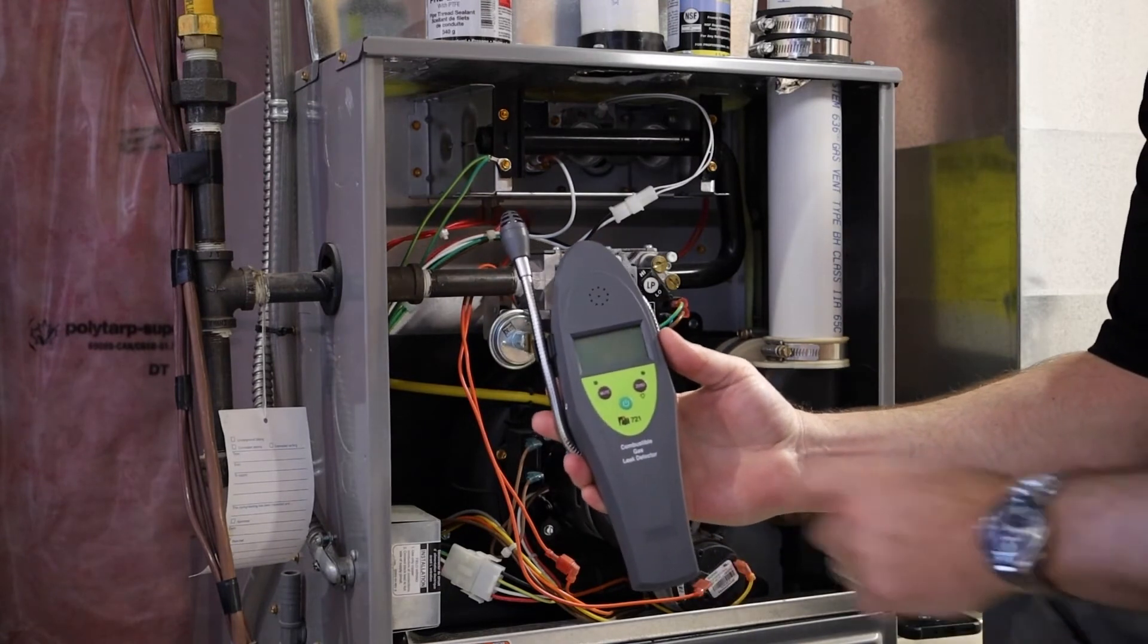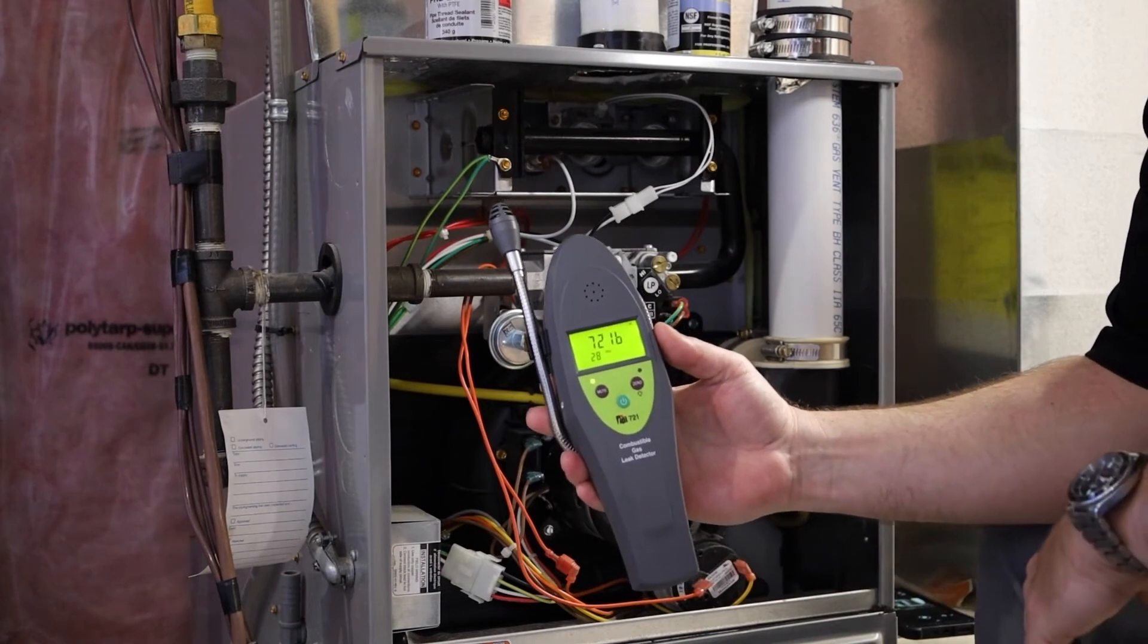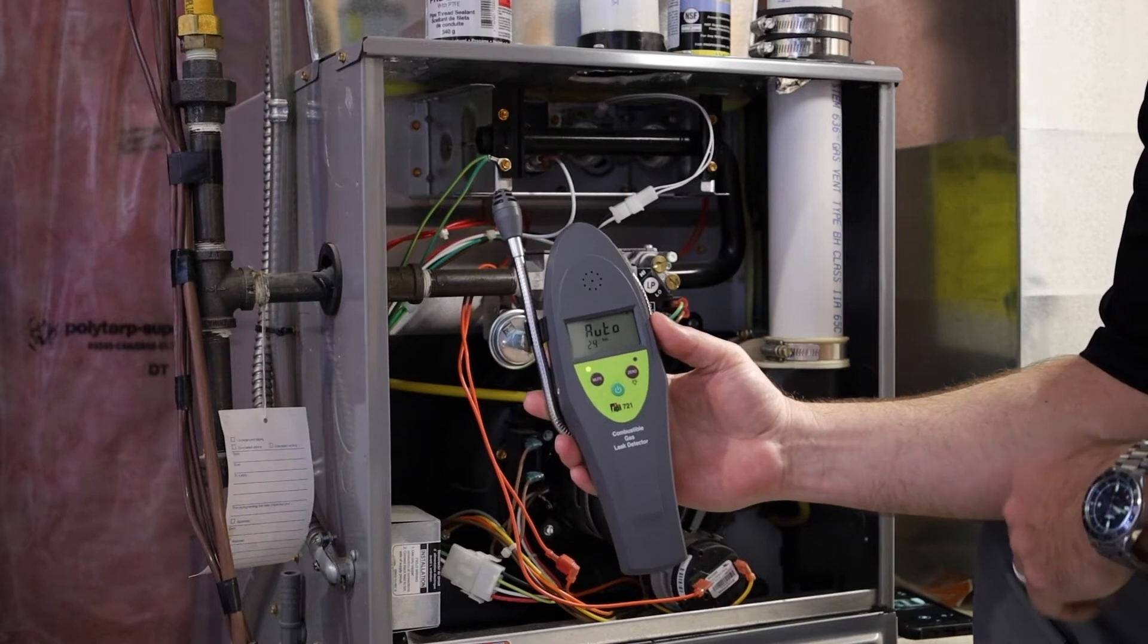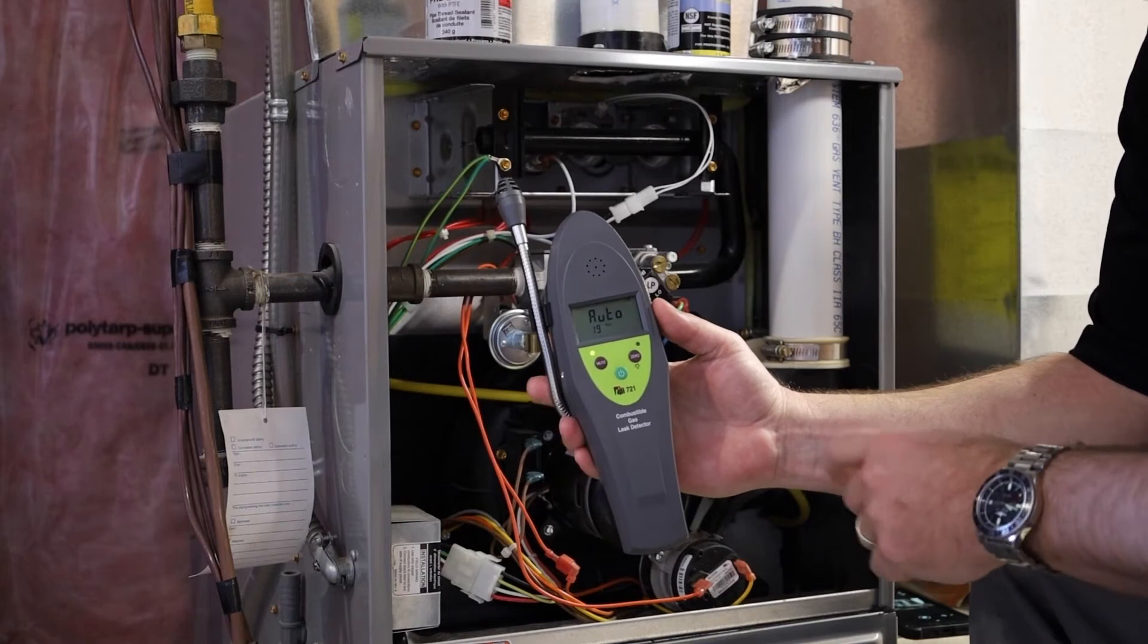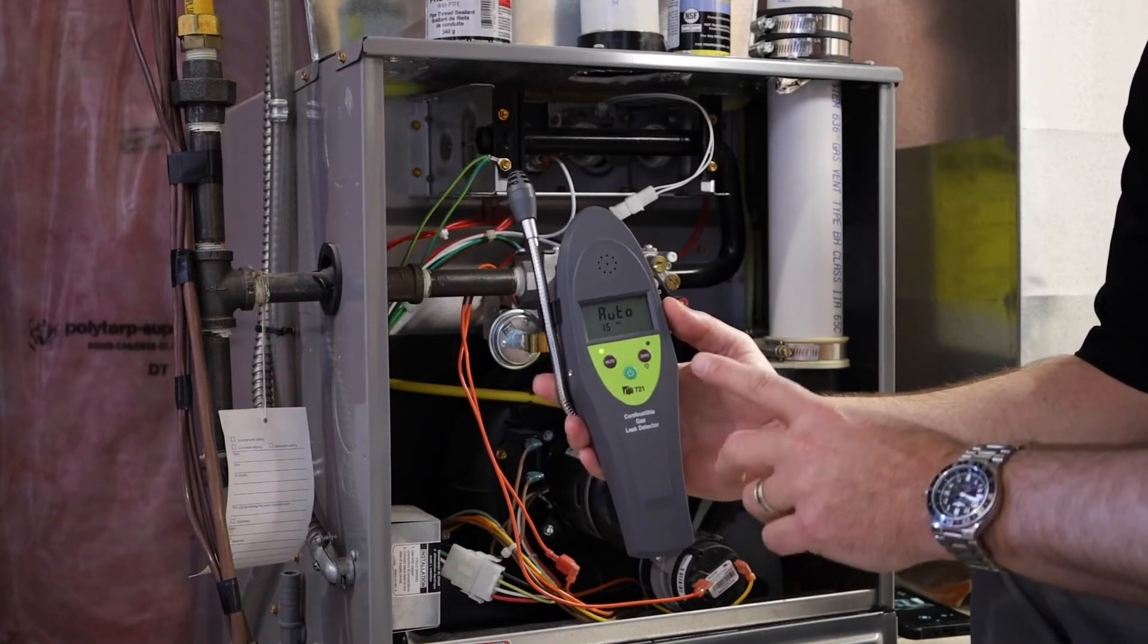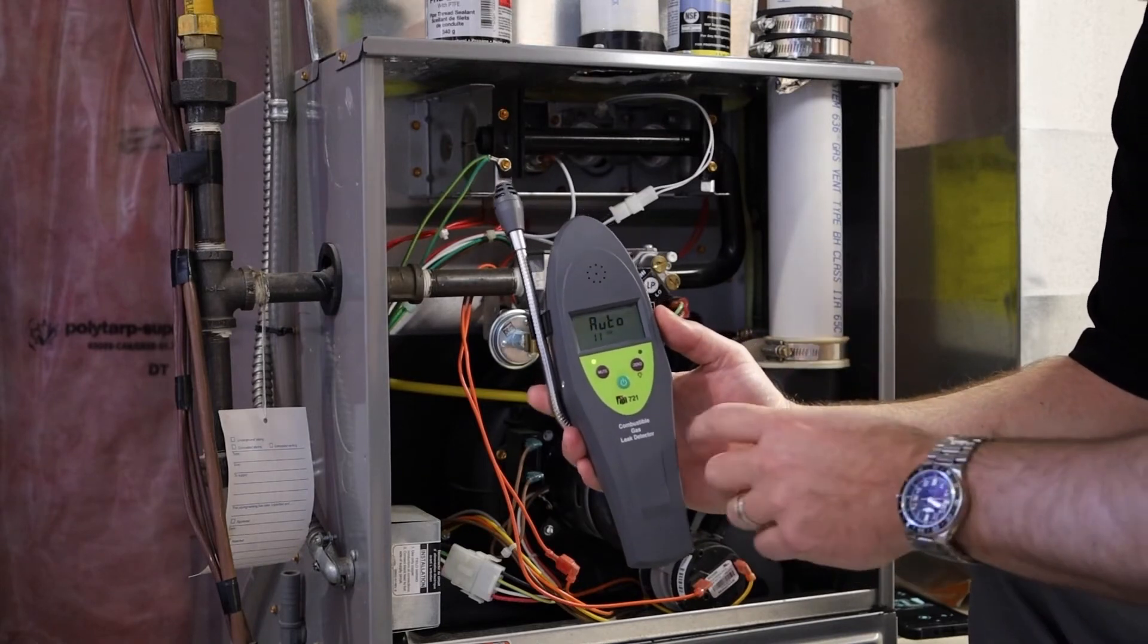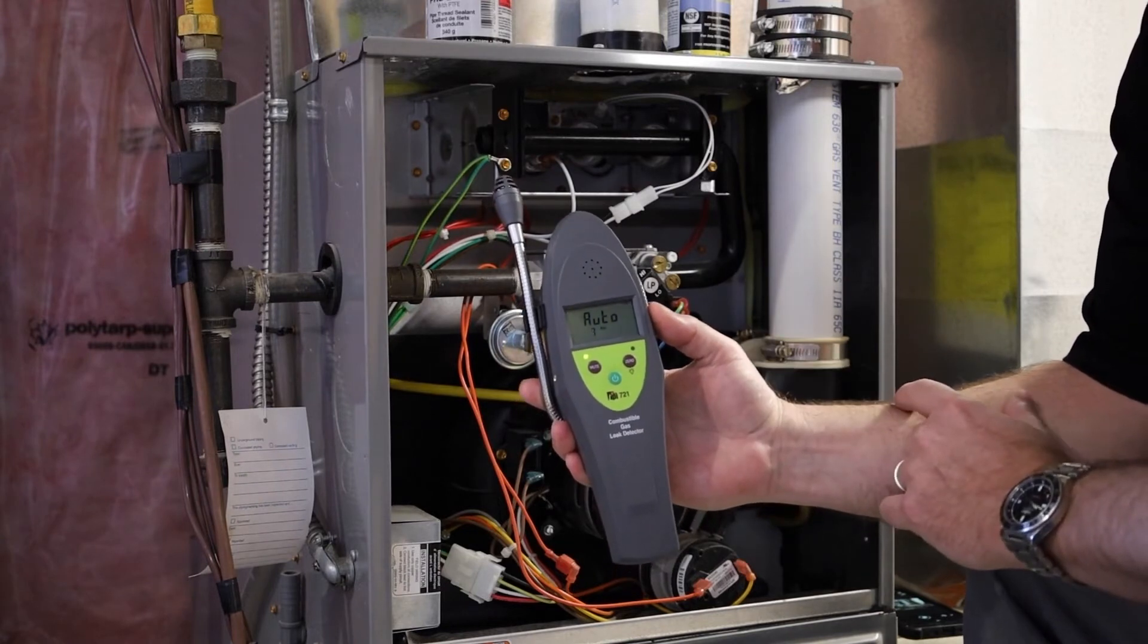Here is the 721. Again, does all the combustible gases. But now we've gone into an LCD display. This one will actually display how big the leak is. It will also do LEL, lower explosive limit. So it will display in percent LEL. So again, I'm waiting for my 30 second countdown to be done. Again, could take longer if the ambient temperature is really cold.